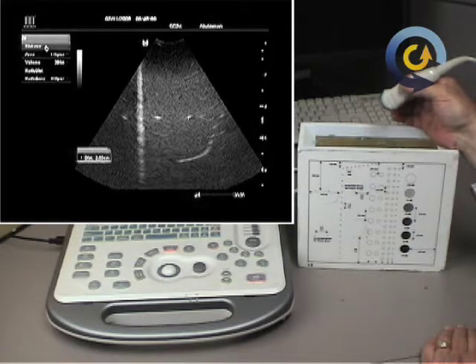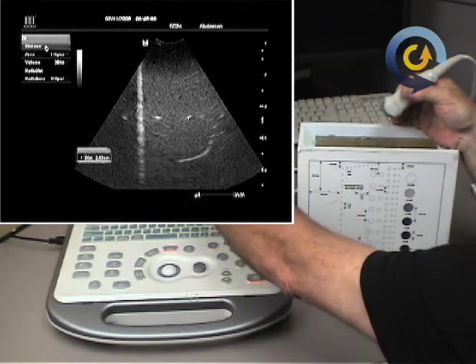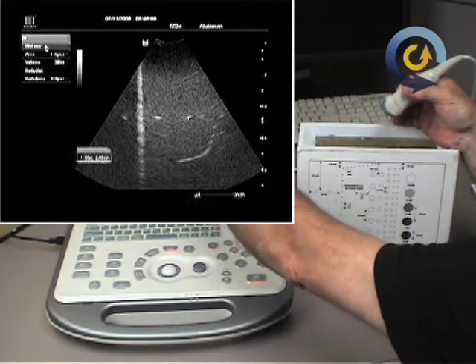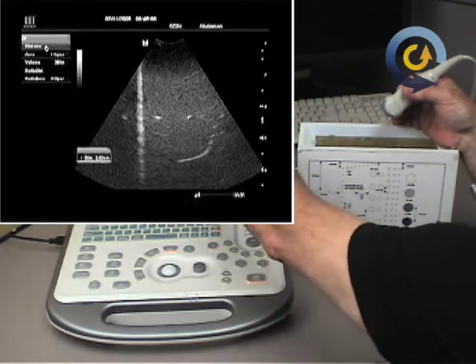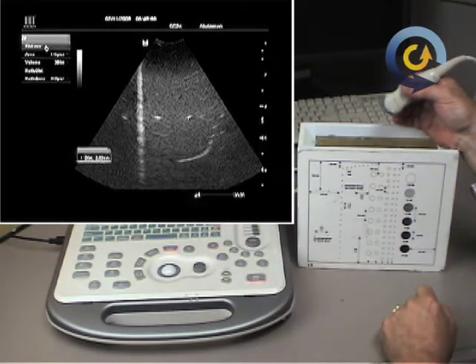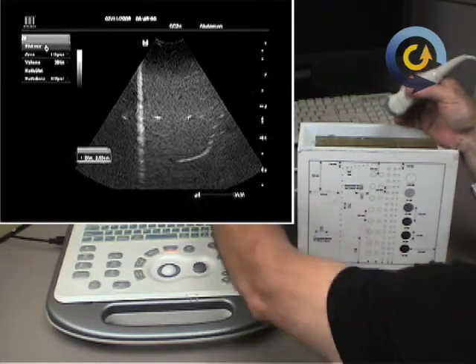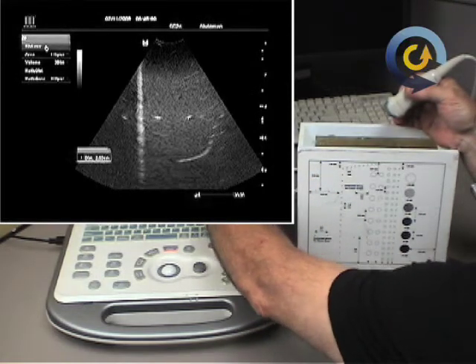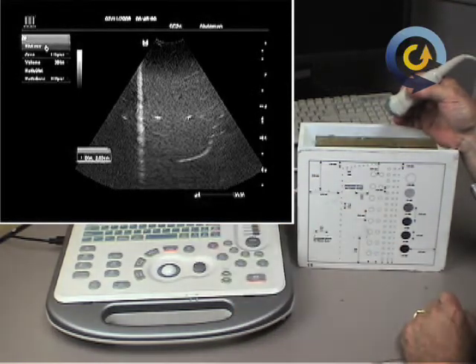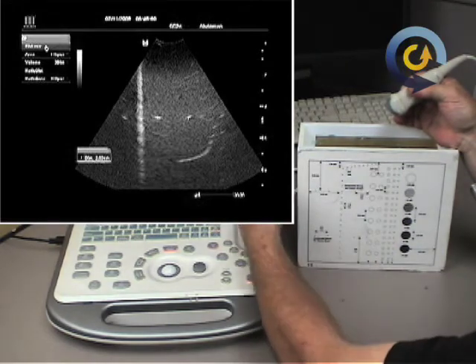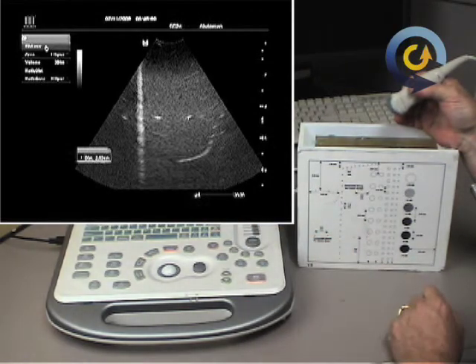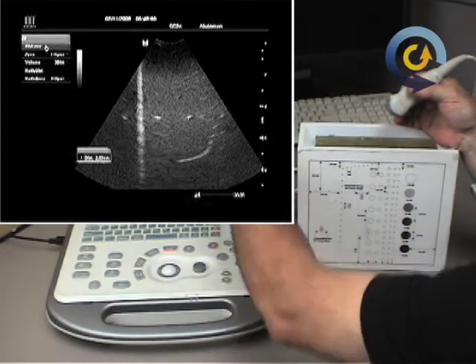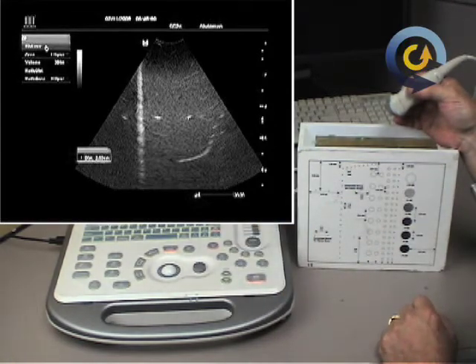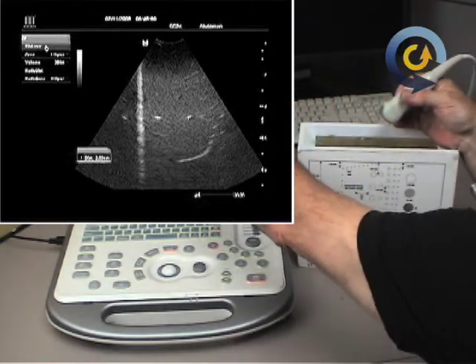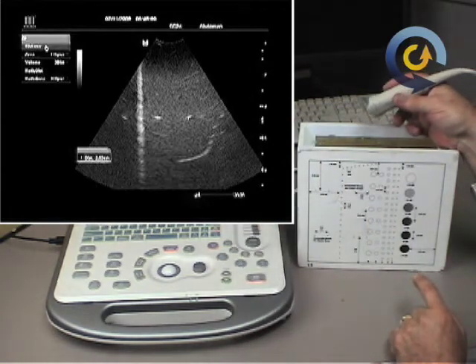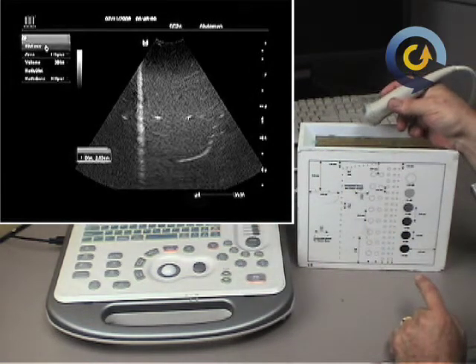The other thing that you're documenting besides the axial and lateral resolution, the axial and lateral measurement, is you're looking for uniformity of the image. That's another thing a phantom is good at showing you. That's a nice uniform image. If it got darker down here, then brighter here, that would show you that you either needed to adjust your settings for your TGC controls, for example, or that you had a problem with the focusing on the system itself. If you looked in the near field and you had dark dropout, that would be indicating you've got an issue with the transducer and likely dead crystals.